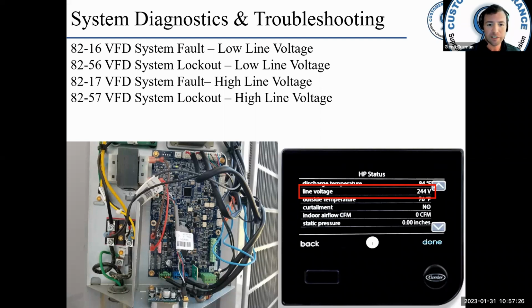8217 is when your voltage rises above 410 volts, then you'll get the 8217. All right. If it happens 10 events in a 1 hour period, then you get the 8257 high line voltage. Now, 410 volts, that's a lot. Some spikes could be causing it, power issues, maybe due to a storm or a surge or something like that.